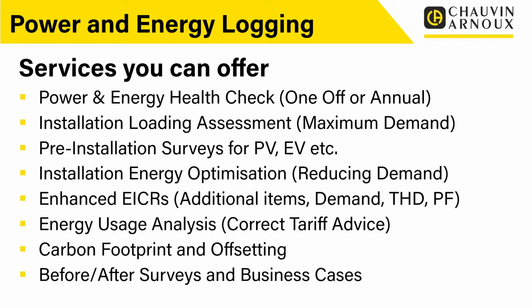For example, there might be a box that says maximum demand, and a lot of the time people just write 100 amps and leave it at that. What we're saying with an enhanced EICR is you could tell your customer you offer an additional service alongside the EICR, where you actually do some load monitoring, measure what the demand is, and give them a graph of that.